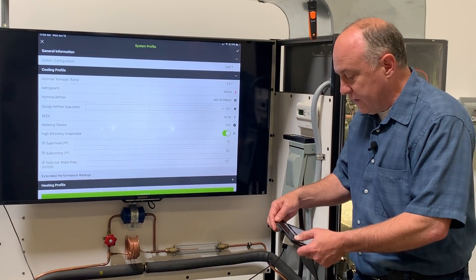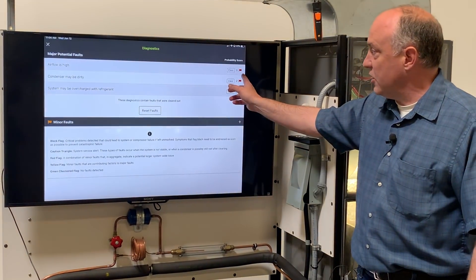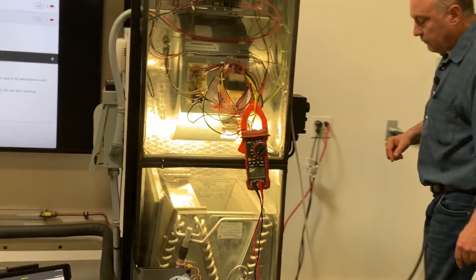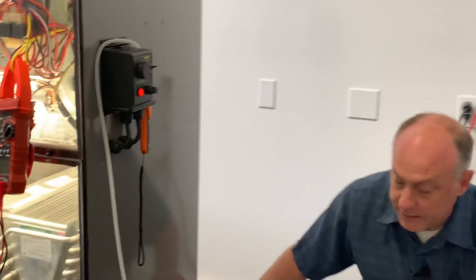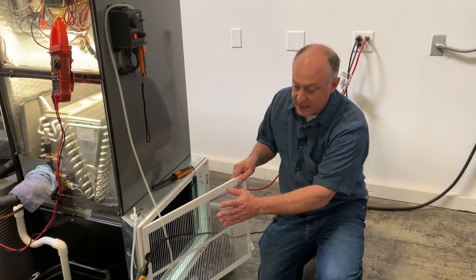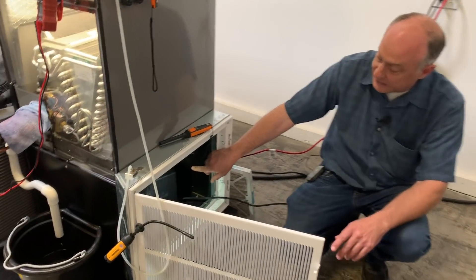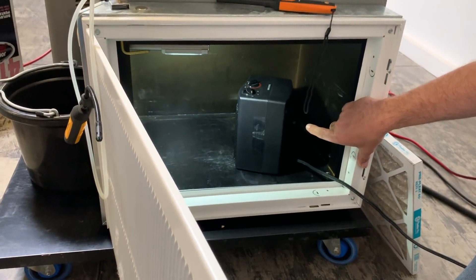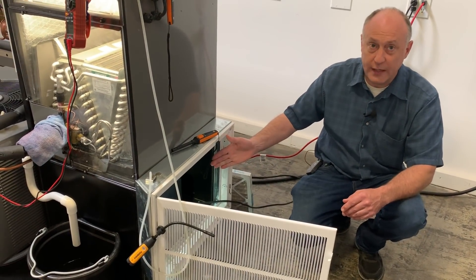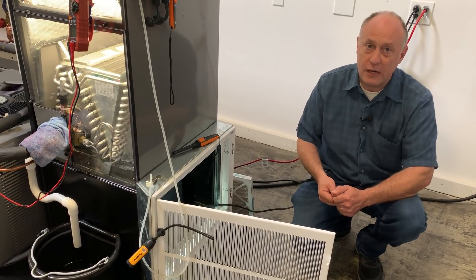Now I want to show you how we do testing, because everything we do here involves real testing. We did say we had return air duct leakage on this — I cleared it out, but I want to go back and show you what we're doing. When you have return air leakage, typically we're making the measurement at the filter grill — in this case, the filter grill in the house up near the ceiling. Inside here, I've got a little electric heater that's just dumping heat into the evaporator coil. It's simulating hot air from an attic leaking into the return air chase and causing a problem with the unit. That's going to drive up the head pressure, it could drive up the suction pressure, and it's going to drive down the temperature split.